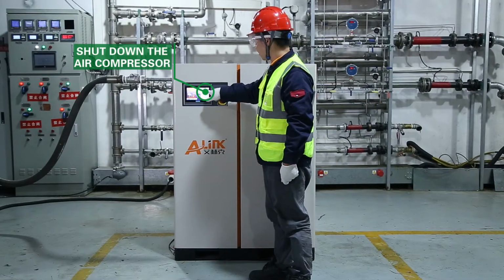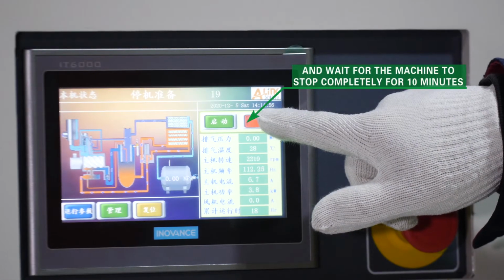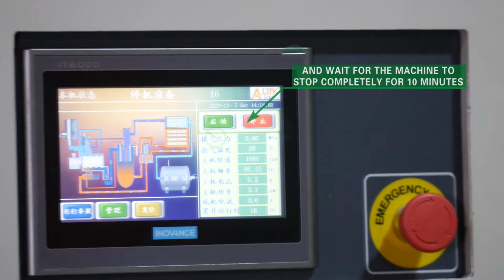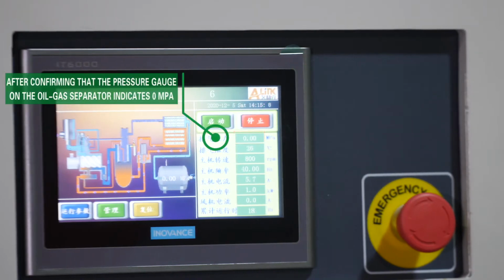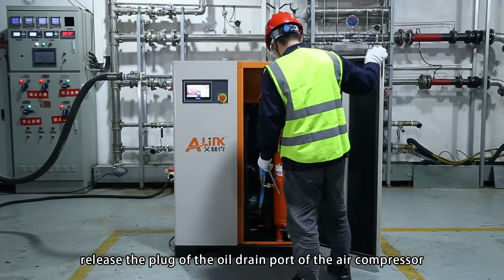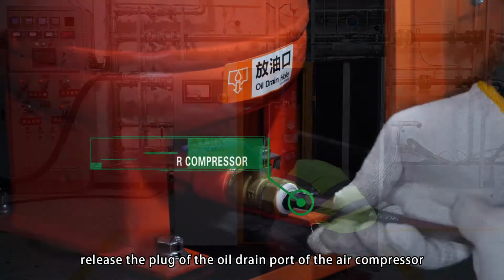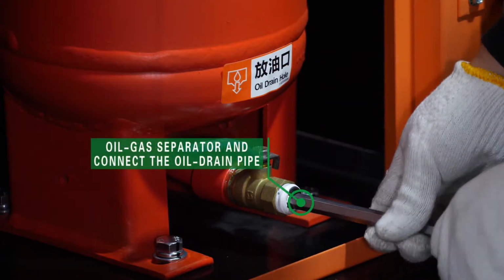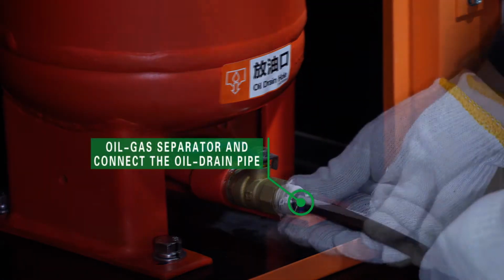Shut down the air compressor and wait for the machine to stop completely for 10 minutes. After confirming that the pressure gauge on the oil-gas separator indicates 0 MPa, release the plug of the oil drain port of the air compressor oil-gas separator, and connect the oil drain pipe.